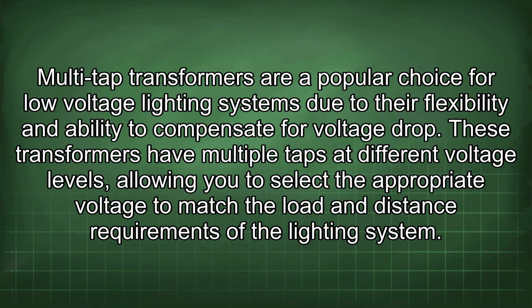Multi-tap transformers are a popular choice for low-voltage lighting systems due to their flexibility and ability to compensate for voltage drop. These transformers have multiple taps at different voltage levels, allowing you to select the appropriate voltage to match the load and distance requirements of the lighting system.